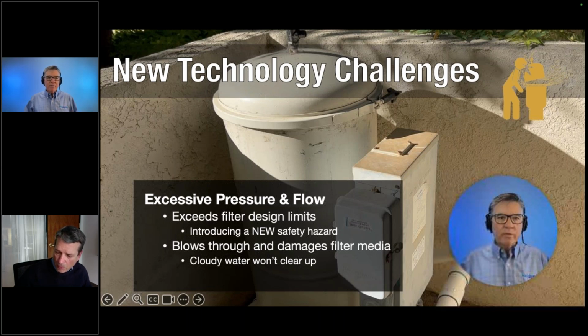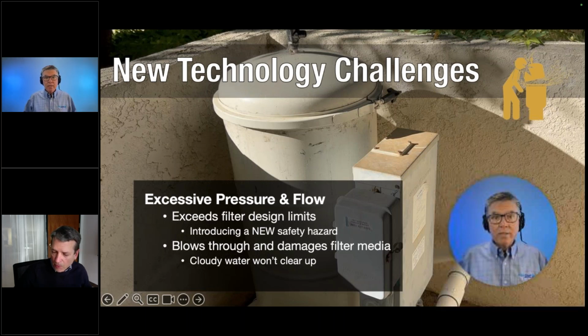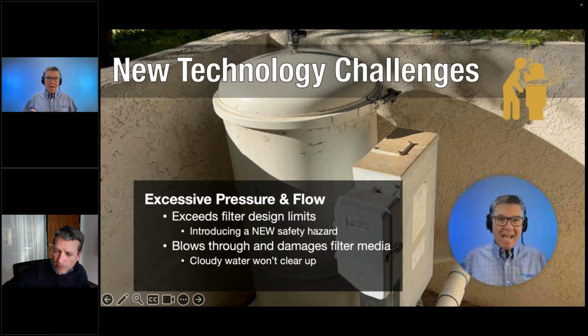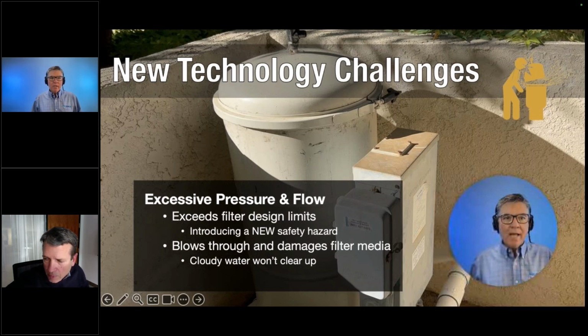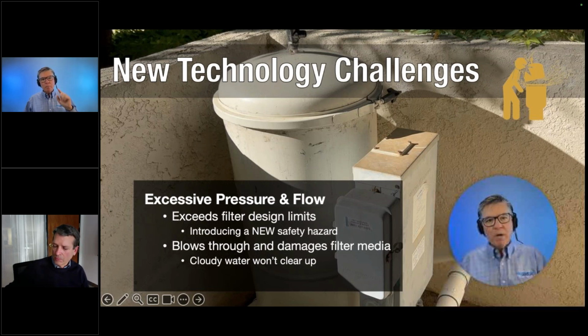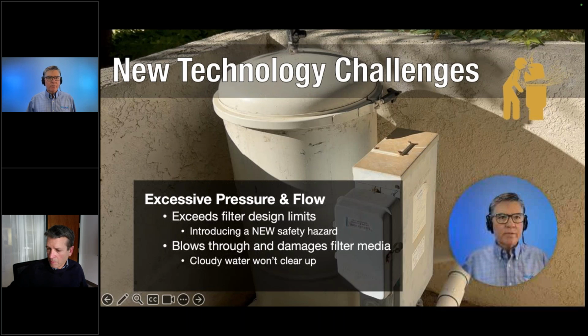And a couple of sand filters, it was blowing through their media, and it was 3 to 4 months, 3 months in the summertime of these pools constantly getting cloudy, so they were draining and refilling. That's a problem. One of them was 250,000 gallons, so that was a serious problem. And it turned out that the pump was actually moving more water than the filter system was capable of handling, and so the solution was to replace the filters or add a second one in one of the cases. So cloudy water can be caused by overpowering your filters.